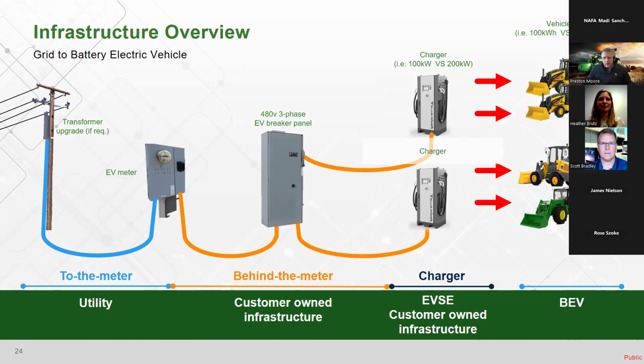But the decision on that vehicle makes a difference on whether, if I need fast charging capability, I select a 100 kilowatt charger or something larger, like a 200 kilowatt charger. Working backwards from the charging station, I might have 3-phase power coming to my site, but at what power level? If that 3-phase is only a 60 or 100 kilowatt connection, and I want to put a 200 kilowatt charger or multiple 200 kilowatt chargers on the site, then all of those decisions back up into the grid connection, such that I have to get the utility company involved. Do I have the right transformers? Do I have the right hardware in the grid infrastructure piece of it?